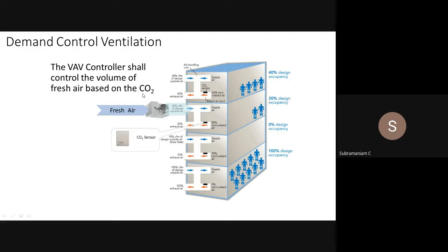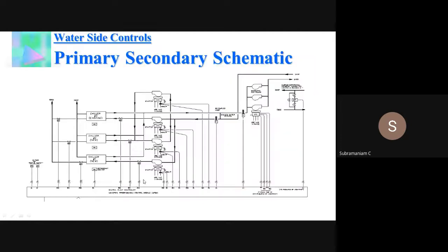So how do we do it? I have to put a CO2 sensor, because if 4 people are there, my CO2 output will be very less. Not like in a cinema theater, where if 400 people are there, your CO2 level is going to go high. If there are only 10 people, like during COVID time, you may not get a CO2 level which is very high. So you don't have to supply that much. ASHRAE standards 62.1 and 90.1 are very good guidelines for fresh air calculation and energy saving logic, what is to be followed there. So this is demand control ventilation, which is required from BMS.